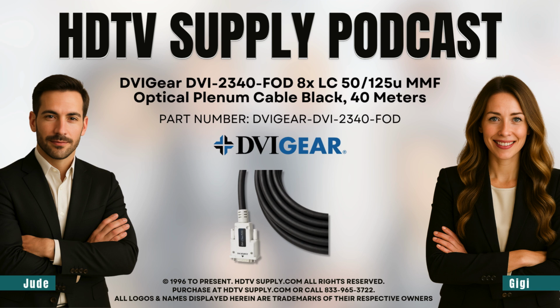So a CMP-rated jacket uses specialized fire-retardant plastics, not just basic rubber. They're often complex fluoropolymers, like Teflon, engineered to self-extinguish and emit virtually zero smoke. The rating dictates strict chemical engineering just to ensure this vital piece of networking gear never compromises a building's fire safety or indoor air quality.